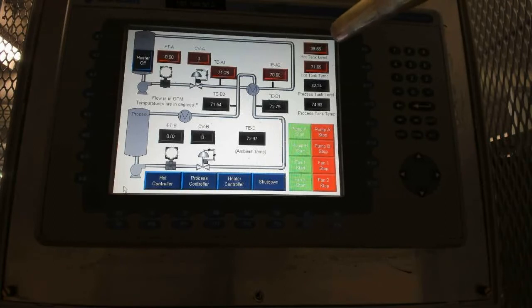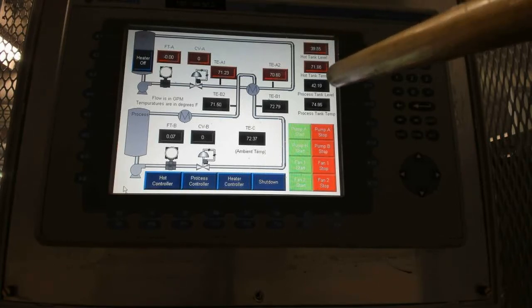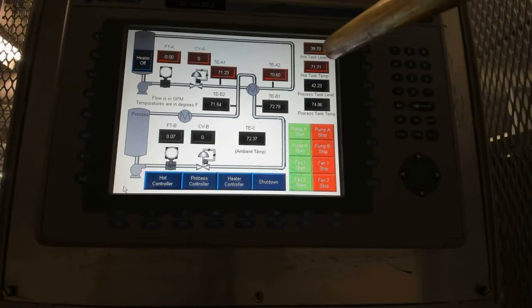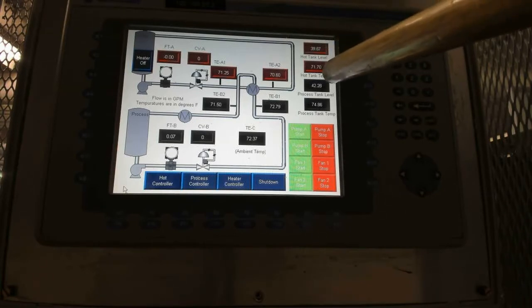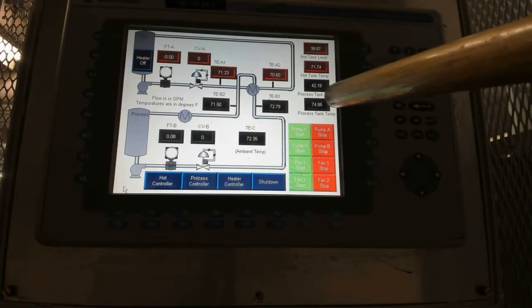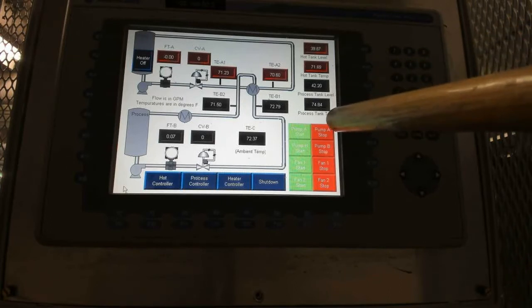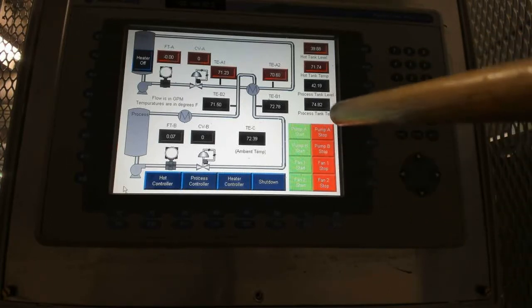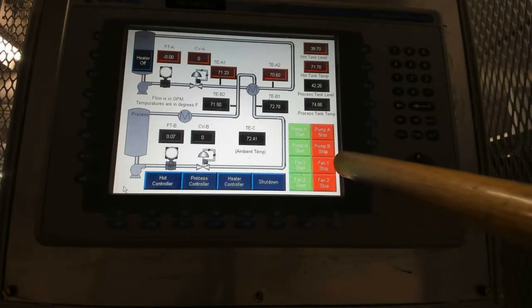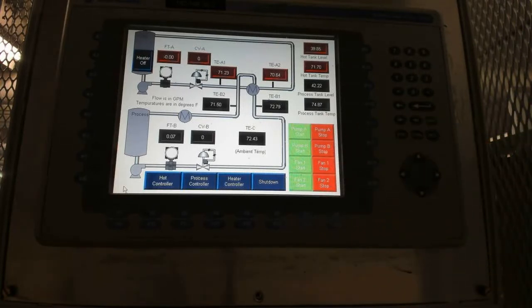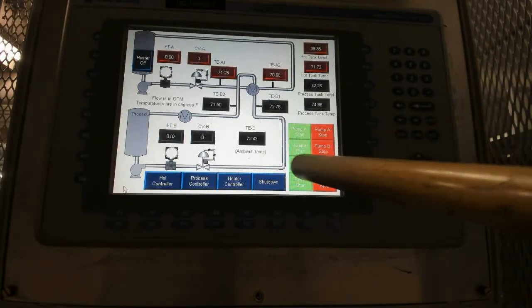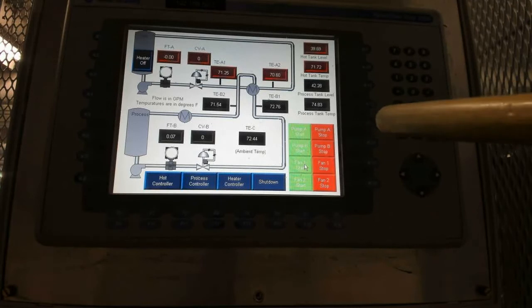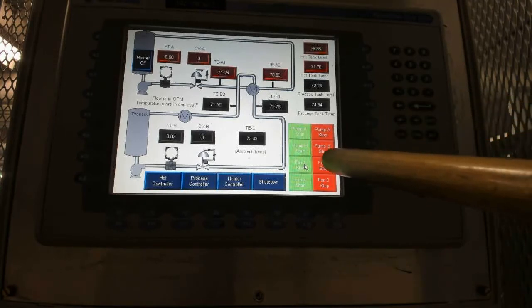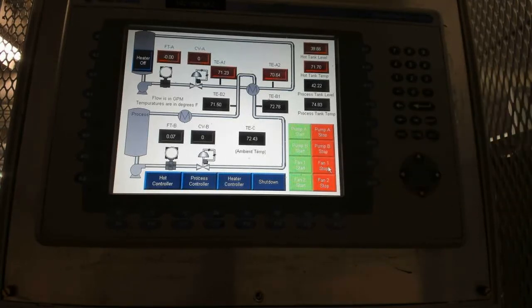And then over here, we have other system parameters. So we have hot tank level, hot tank temp, process tank level, process tank temperature. And then here we can start the different pumps. Or here, like I was saying, there's two sets of fans on this heat exchanger over here. And so an operator could hit, and you can hear that fan kick on, or I could turn it off there. And so that's our heat extraction.